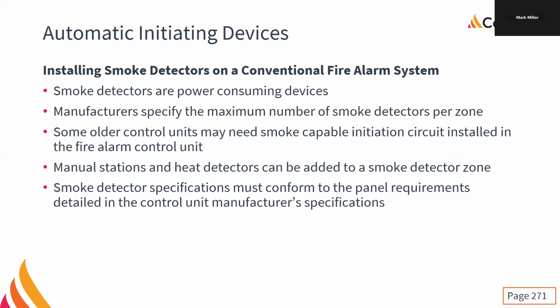Unlike our manual stations and heat detectors, because those are non-power consuming devices, they are mechanical in nature, so we can put as many as we want on the zone. Not an issue. We can add pull stations and heat detectors to a smoke detector zone, no problem at all.